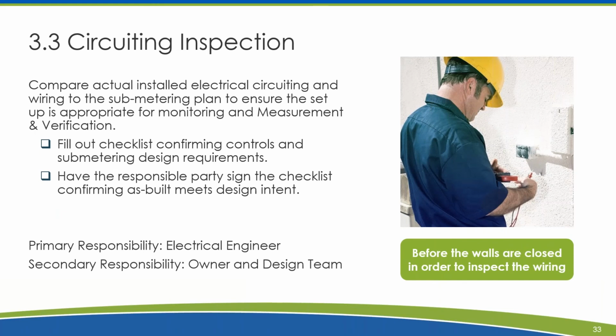We also, to carry through this idea of making sure we're monitoring certain end uses for the project, provide a circuiting inspection in phase 3, and we require that controls and submetering are evident and carried through from the construction phase. We have a checklist that we ask the electrical engineer to complete, making sure the electrical circuiting and wiring is set up per the submetering plan. This is also identified in the measurement and verification plan, the previous deliverable.